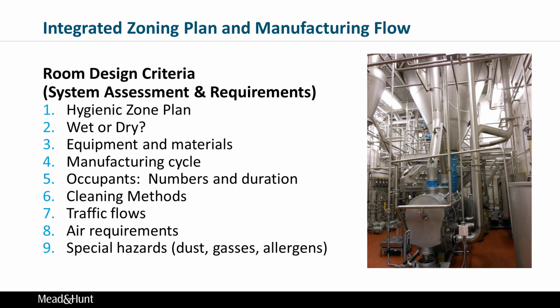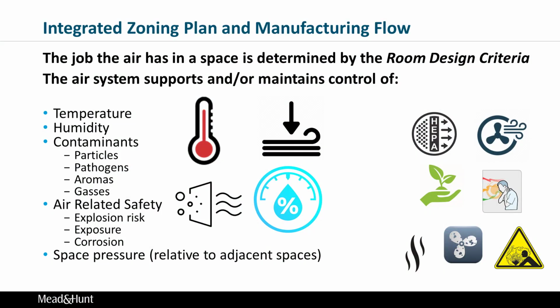And then what do I need my air to do? And then there are other things, dust, gases that may bring aromas, or allergens. So really the job the air has in a space is determined by that room design criteria. The air system supports and or maintains control of those things on the left. Usually temperature and humidity are number one and number two, and then the space pressure. If you're in a sensitive area, you always want to have slightly elevated pressure so that when a door's open or when there's a penetration in the wall somewhere, the air from that room is going to go into a room that's less sensitive.